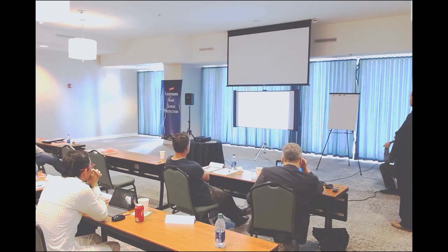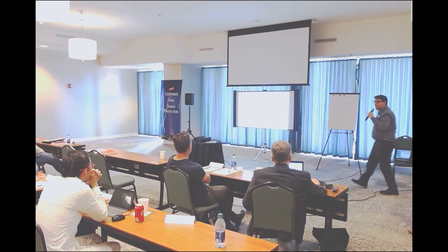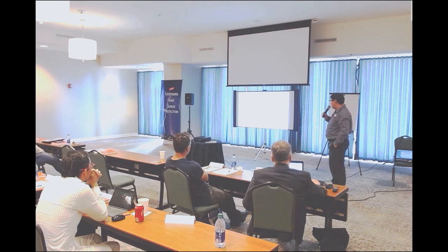So just have a look here. So there you have an IEC solution for a structure. It utilizes, what, 4-6 lightning rods. Like I said, it was calculated at a certain distance to make sure that the rolling sphere covers it exactly the way it should. And what you see here is the equivalent NFPA solution. So you see what I mean in terms of material use, in terms of installation effort. All of those things are a significant factor when you take into consideration the two different design approaches.